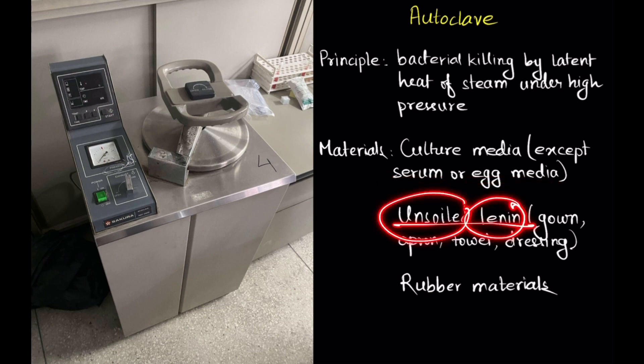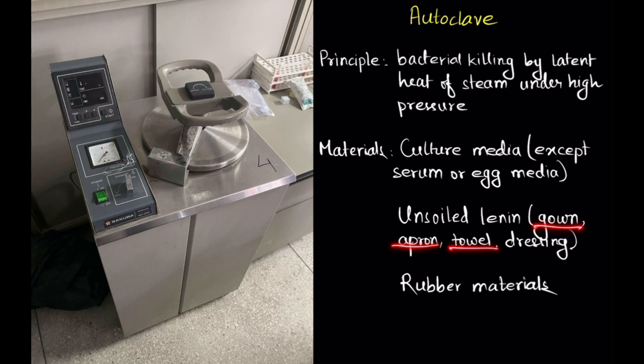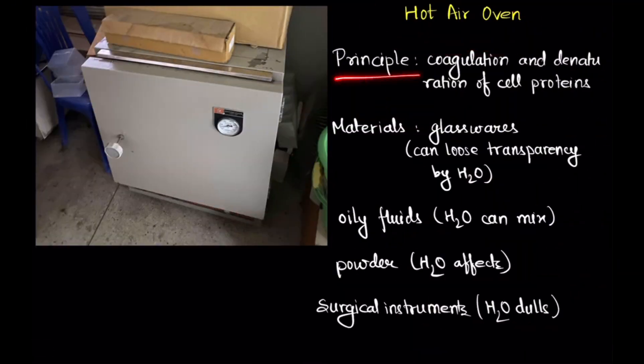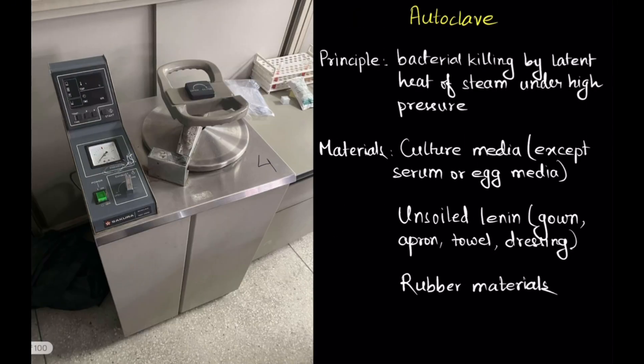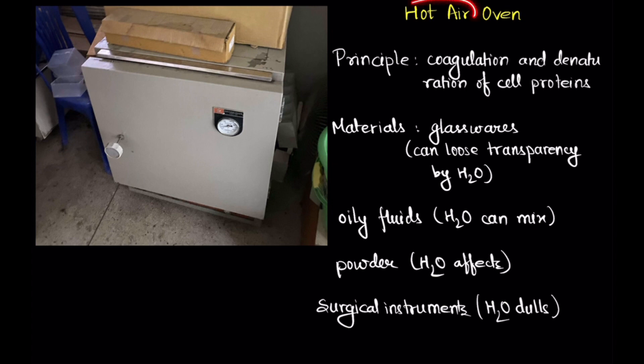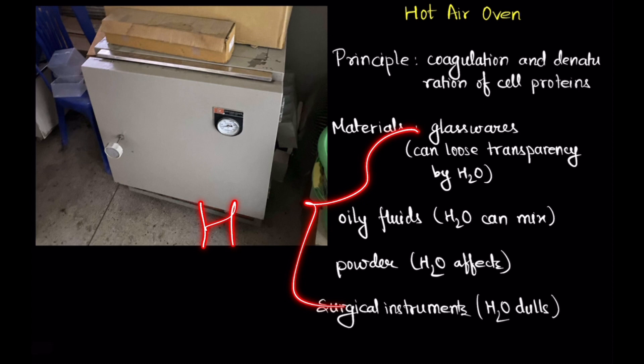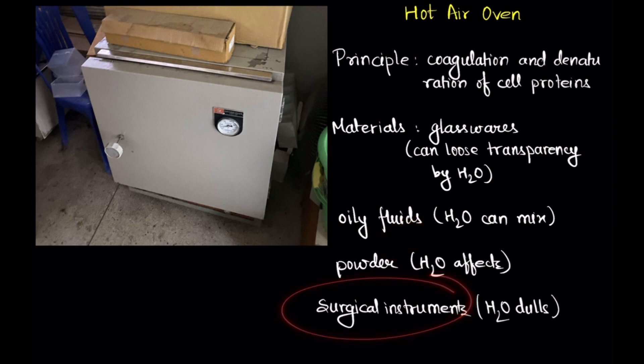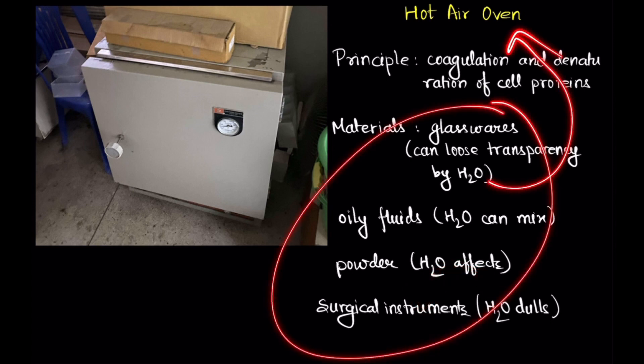Unsoiled linen — linen refers to dressings, and unsoiled means not contaminated by feces, stool, urine, or sputum — such as gowns, aprons, towels, dressings, and rubber materials are sterilized in the autoclave. The principle of hot air oven is coagulation and denaturation of cell proteins. In autoclave, water is used — the latent heat of steam is used. In hot air oven, water is not used; electrical energy is converted to heat energy. The materials sterilized here are those that cannot be sterilized by autoclave or are affected by water: glassware (which can lose transparency due to water), oily fluids (since water cannot mix with oil), powders (affected by water), and surgical instruments (which can become dull due to water). That is why these materials are sterilized by hot air oven.